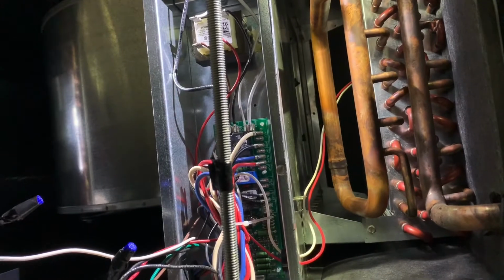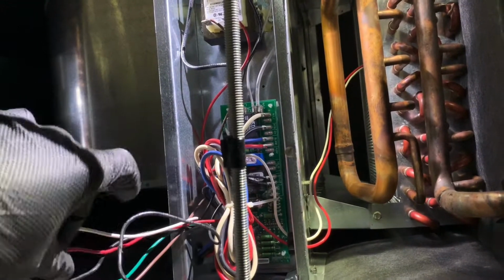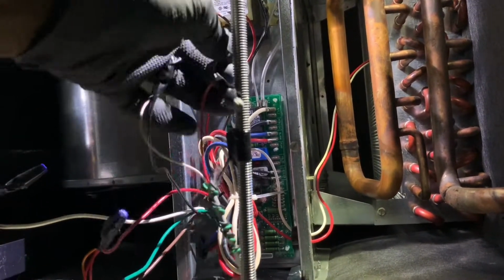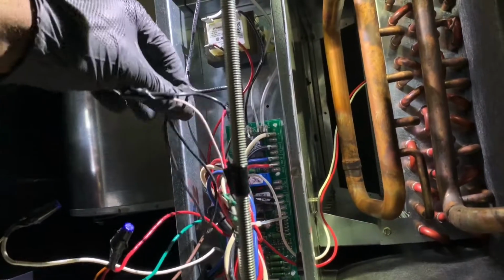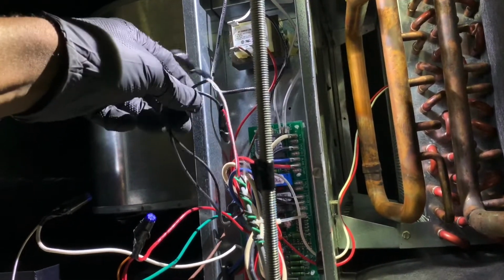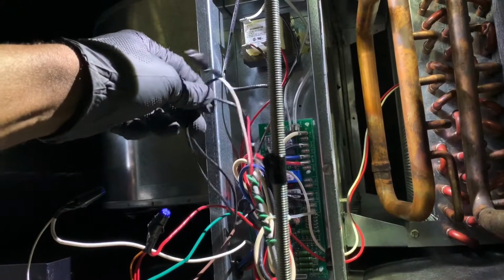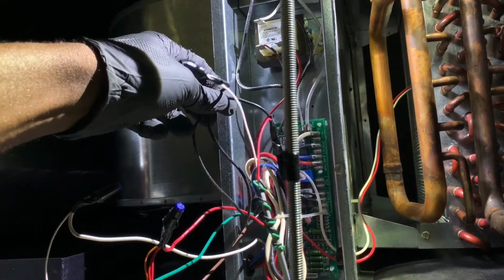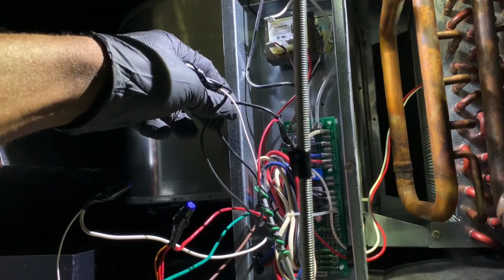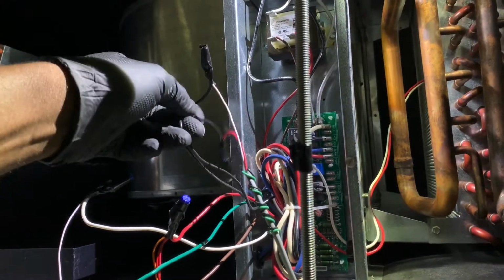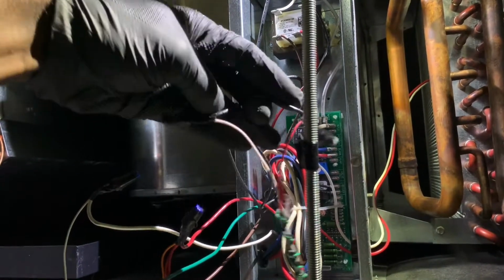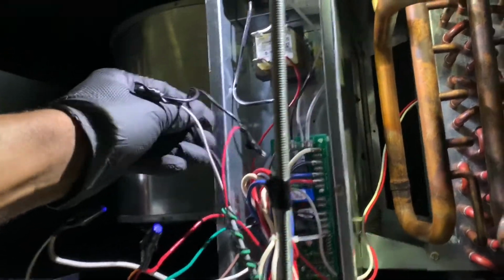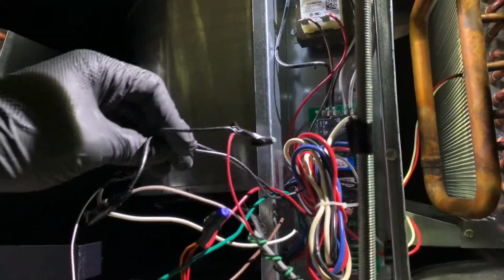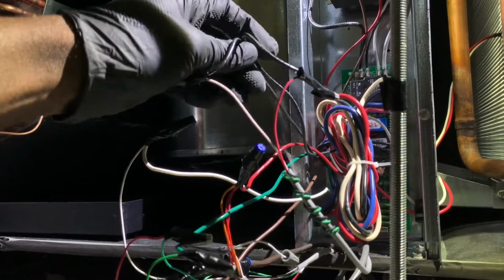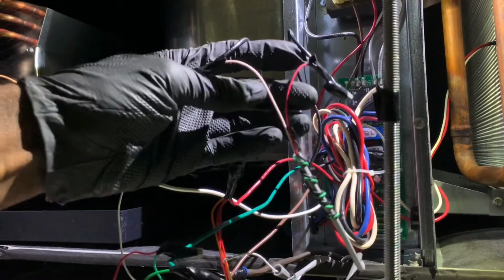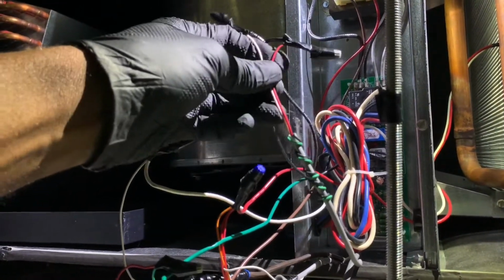And then, there's two black wires. There's one right here. There's these two black wires right here. These are TT, and are basically just going to activate your zone pump on your boiler, or activate your boiler. All right, so these two wires are going back to my boiler. This is from TT, the black wires from the control board, and red and white goes to the boiler.